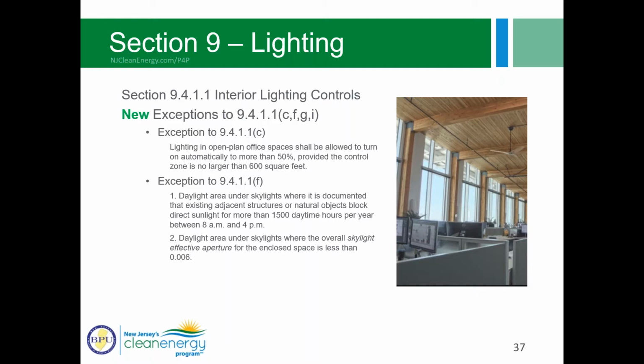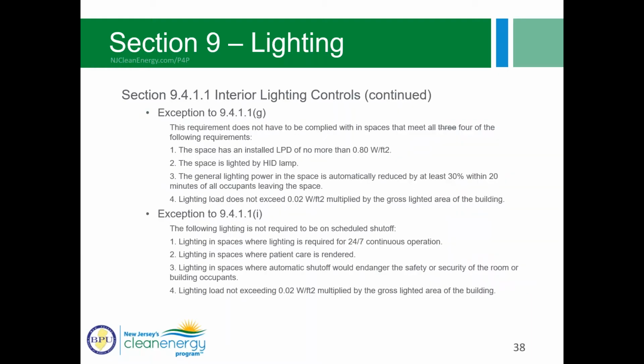Item F applies to automatic daylight responsive controls for top lighting with photocell control. And it's exempt for spaces that have adjacent structures that shade the area for a significant period of time, or for spaces with low overall skylight effective aperture. And again, that skylight effective aperture is a pretty solid equation, with lots of variables that are described within the definitions section. So you can check to see if that exception may apply to your project.